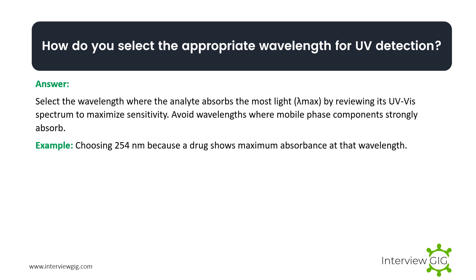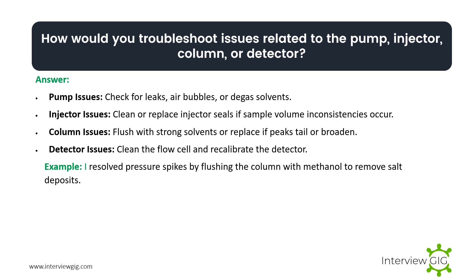How do you select the appropriate wavelength for UV detection? Select a wavelength where the analyte absorbs the most light by reviewing its UV-Vis spectrum to maximize sensitivity, and avoid wavelengths where mobile phase components strongly absorb. Example: choosing 254 nm because a drug shows maximum absorbance at that wavelength.